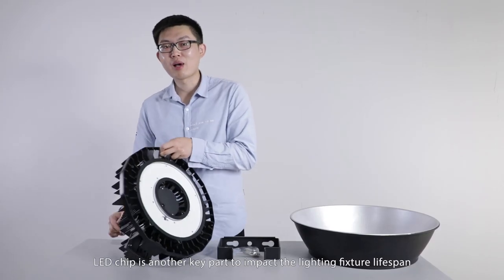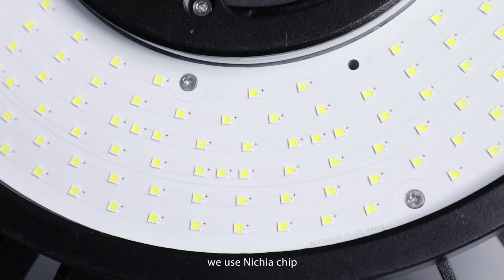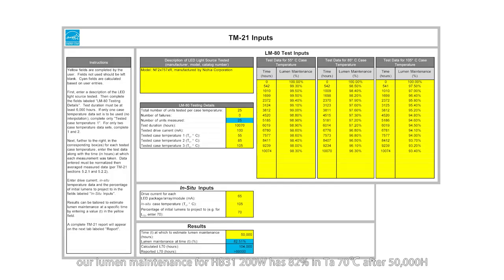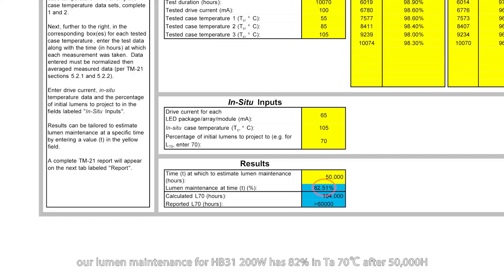The LED chip is another key part impacting lighting fixture lifespan. We use a Nichia chip. From the TM-21 test report, our lumen maintenance for the HB31 200-watt holds at 82% in an ambient temperature of 70 degrees after 50,000 hours.